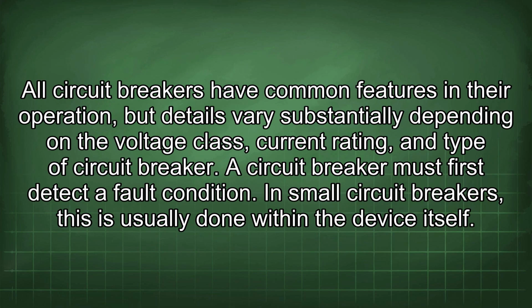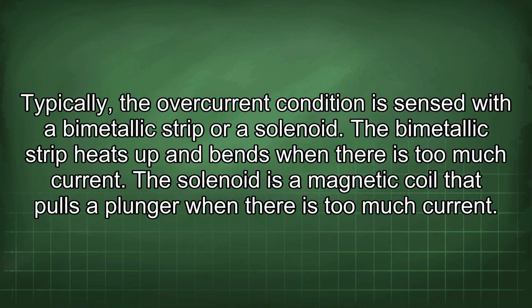All circuit breakers have common features in their operation, but details vary substantially depending on the voltage class, current rating, and type of circuit breaker. A circuit breaker must first detect a fault condition. In small circuit breakers, this is usually done within the device itself. Typically, the overcurrent condition is sensed with a bimetallic strip or a solenoid. The bimetallic strip heats up and bends when there is too much current. The solenoid is a magnetic coil that pulls a plunger when there is too much current.